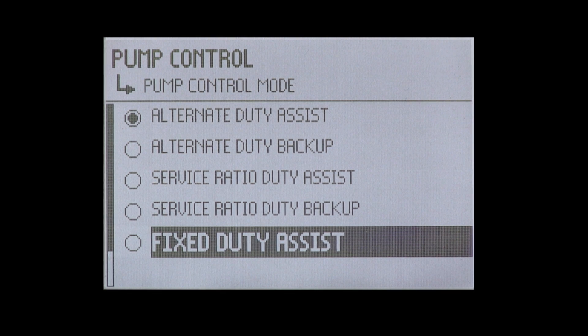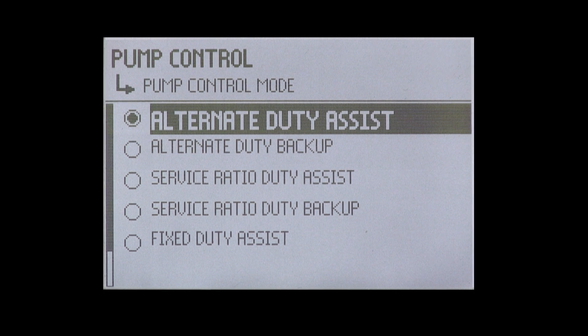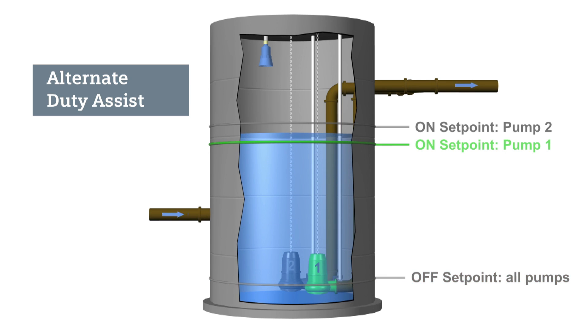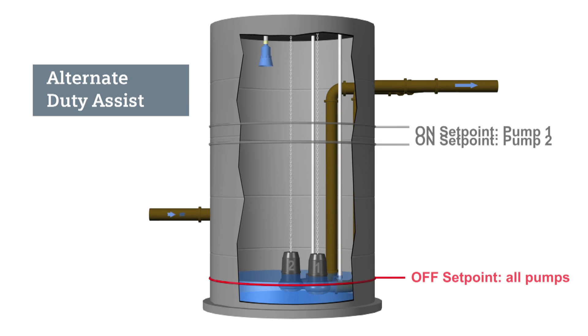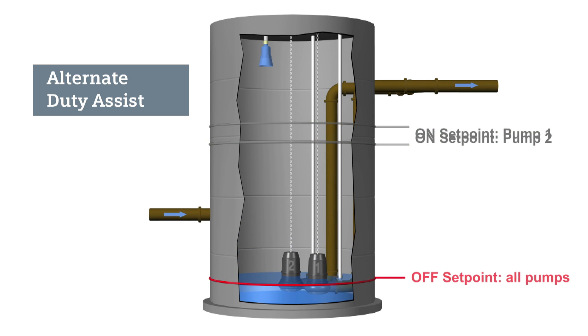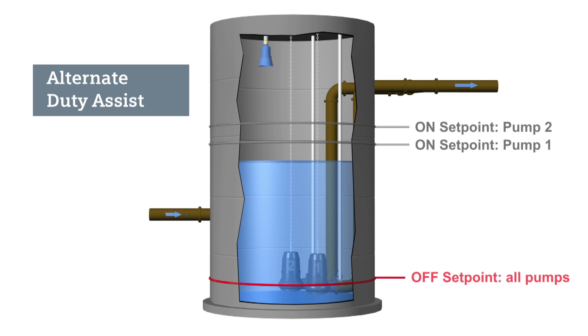The alternate duty assist routine rotates between both pumps to control the liquid level. Pump one will start first. If it cannot keep up with the inflow, then pump two will turn on and assist pump one. Both pumps will run until the liquid level reaches the pump off setpoint. On the next cycle, pump two will be the first pump to start, and pump one will assist pump two if necessary. The starting pump will continue to alternate between pump one and pump two after each filling cycle.